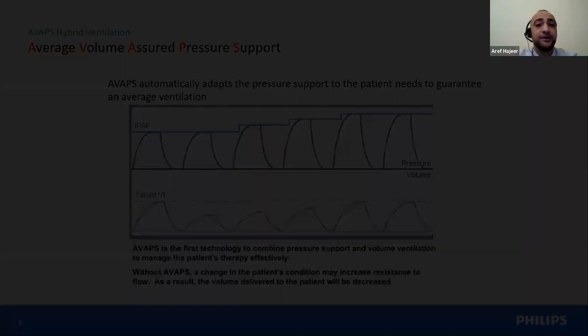And as I said, it's an average volume assured pressure support. And in this case, you have to set three things. Let's take an example of BiPAP ST, which is a pressure mode where you regularly set an IPAP, EPAP, and backup rate. Once you activate the Avaps feature, you add it on, and then you will have an IPAP maximum, IPAP minimum, and then you have a fixed EPAP, and then you have a target tidal volume.